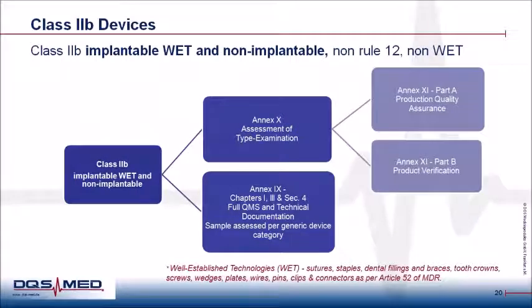Class 2B implantable, WET, and non-implantable, non-Rule 12 and non-WET. WET are the exceptions of well-established technologies which involve sutures, staples, dental fillings, braces, tooth crowns, screws, wedges, plates, wires, pins, and so on and so forth, as listed by the Article 52 of the MDR. The basic conformity assessment route remains the same. That is either Annex 9 or Annex 10 along with Annex 11 Part A or Part B. Here, the technical file will be assessed based on per generic device category assigned.